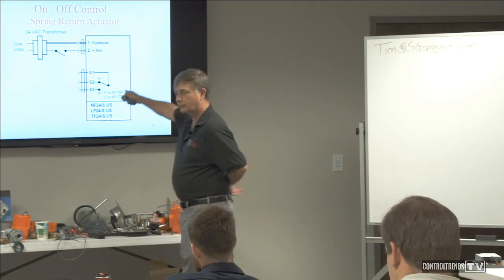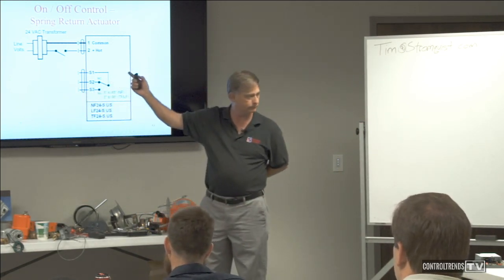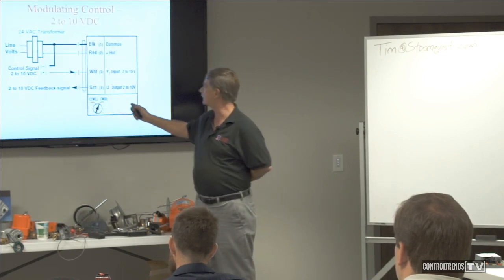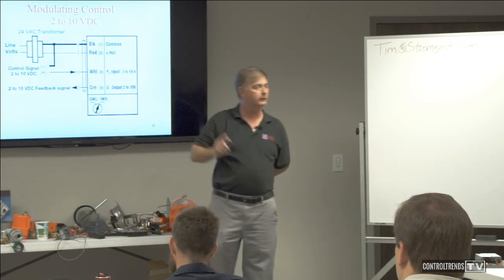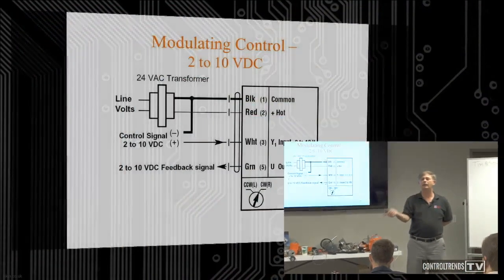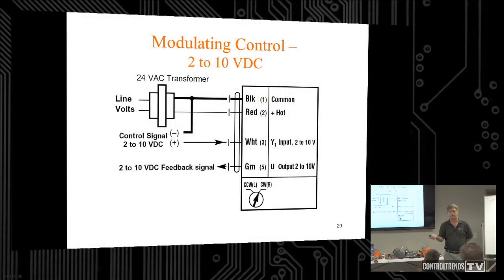All right, so end switches. Everybody can relate to this? Simple? All right. Then let's look at this feedback. This is a little different. This is an analog feedback. So we've got a 0 to 10 or 2 to 10 signal coming back from our actuator. This will tell us not that it's all the way open or all the way closed, but at what position it is. And sometimes our controllers want to know. Just depends on the controller.